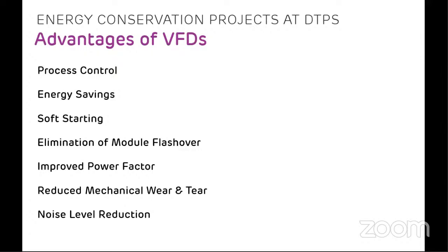Along with power saving, VFDs also give other advantages. The major advantage is process control. For example, if you have a vessel and you want to control the level, then the VFD will control the flow by varying speed and the level of the vessel will be controlled. Then the other obvious major benefit is energy saving. The third benefit is soft starting.